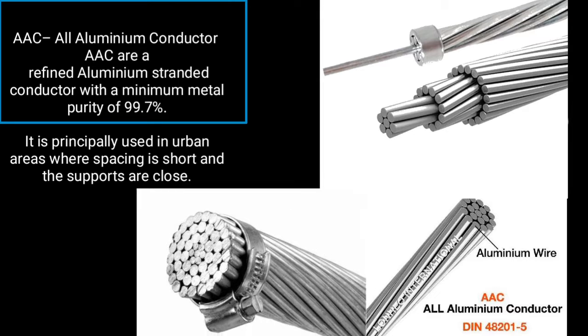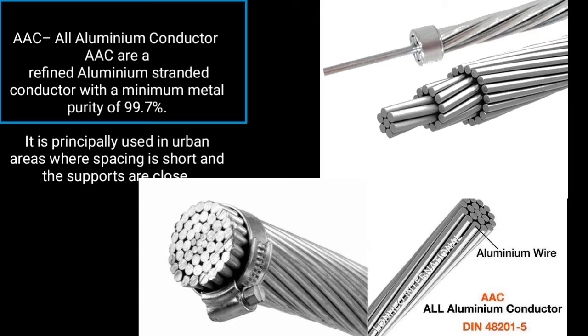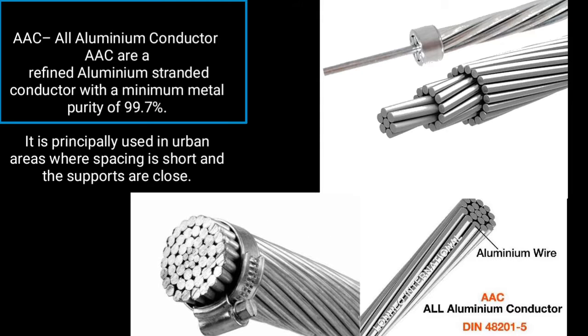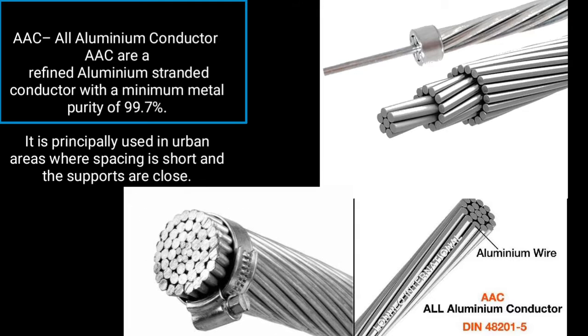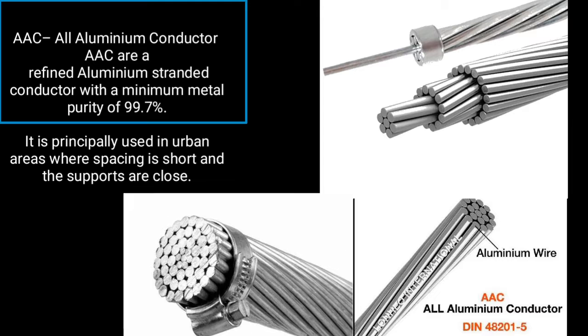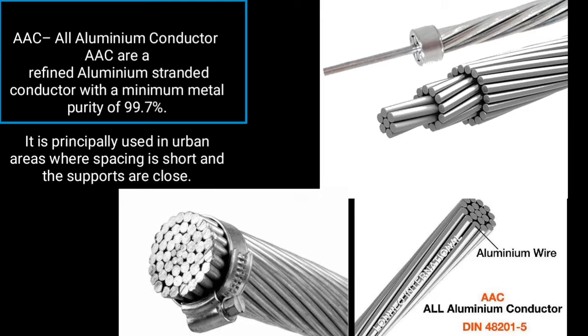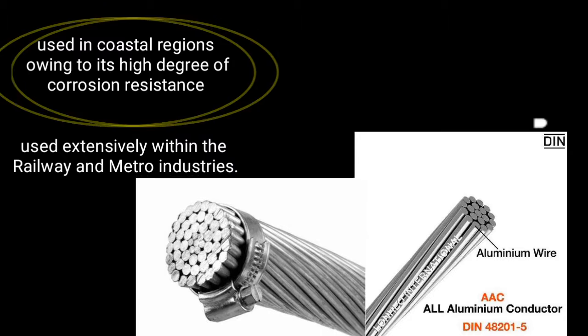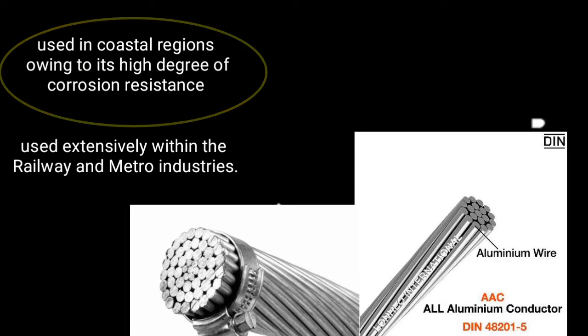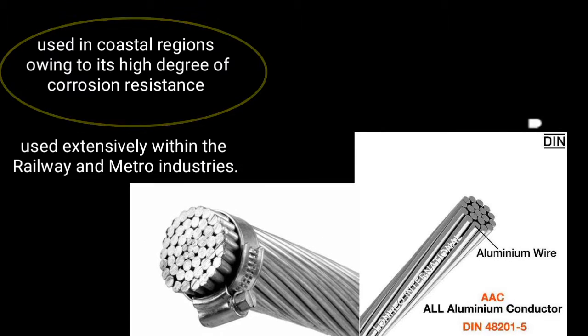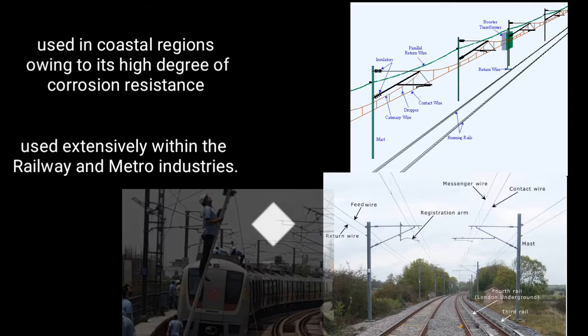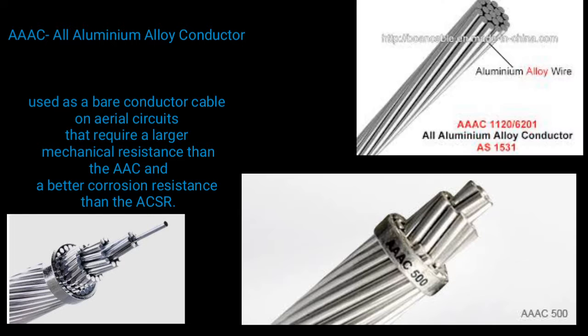AAC is a stranded conductor with a minimum aluminium purity of 99.7%. It is principally used in urban areas where spacing is short and the supports are close. It can be used in coastal regions owing to its high degree of corrosion resistance, and is also used extensively within the railway and metro industries.